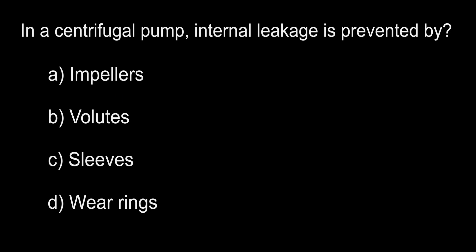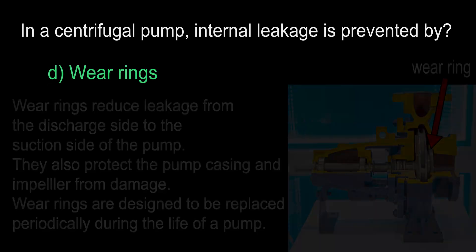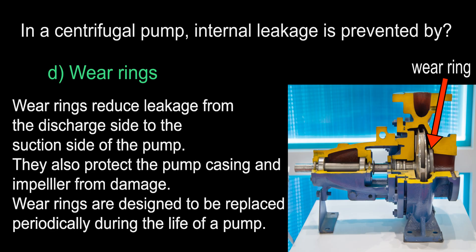In a centrifugal pump, internal leakage is prevented by: A. impellers, B. volutes, C. sleeves, D. wear rings. The answer is D, wear rings. Besides protecting the impeller and pump casing, a very important part of wear rings is to improve pump efficiency. In a centrifugal pump, water from the high-pressure discharge side will want to flow back to the low-pressure intake side — the wear ring helps prevent that. If you notice a pump not performing as well as it used to and there is no other obvious issue, check the wear ring, as they degrade over time and must be replaced with a specific size per the maintenance manual.